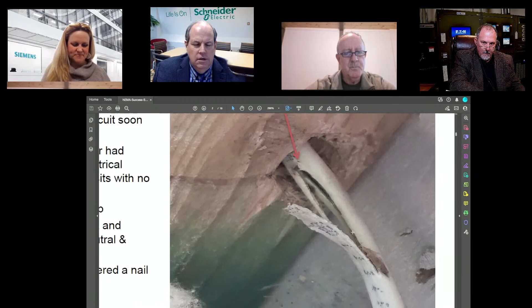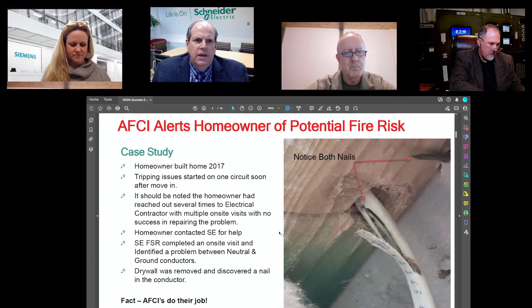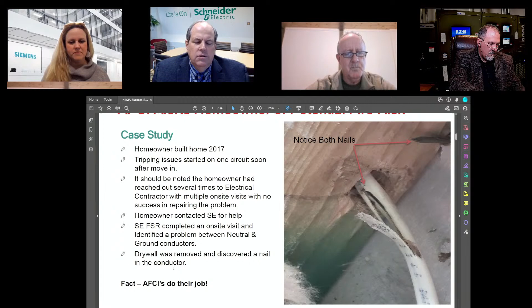So what they ended up doing is they contacted the manufacturer of the AFCI, which in this case was our company, and we sent a services person out to work with the electrical contractor with some equipment. We identified from that visit that the AFCI was tripping based on a problem between neutral and ground conductors - it was seeing an arc fault that could cause a fire.